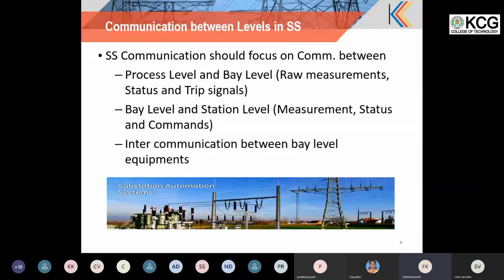Then moving on to communication between the layers in the substation. We need to have communication from the process level equipments to the bay level equipments. That is, at the process level you have transformers, breakers, everything, and we need to send these raw measurements from the CTs and VTs to the bay level equipment, including the trip and status signals. Then from bay level to station level, all the IEDs need to send their SOE, status, everything to the station level. So this constitutes measurement, status and command from the bay level to station level.